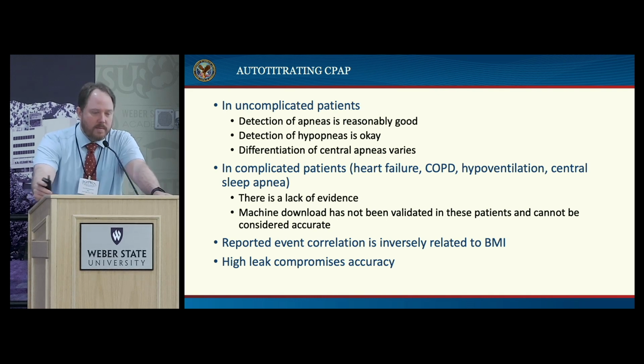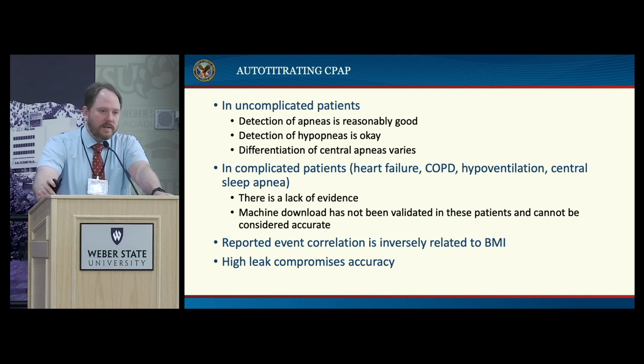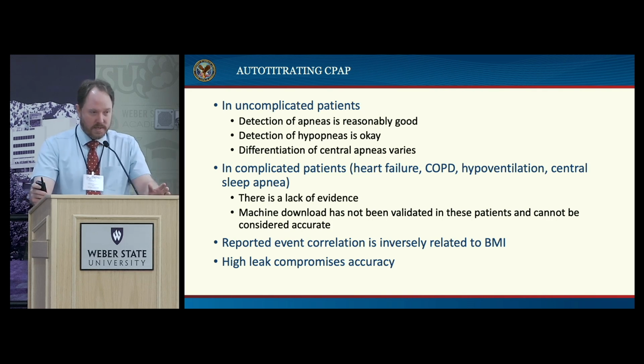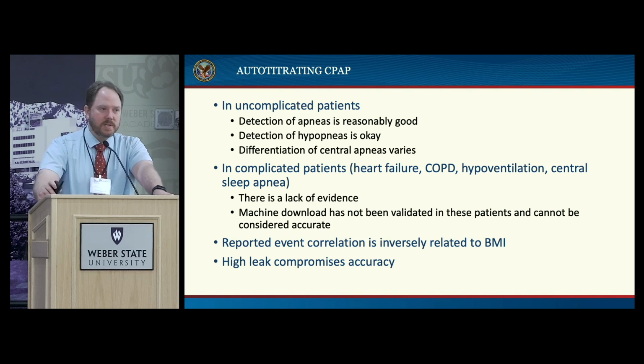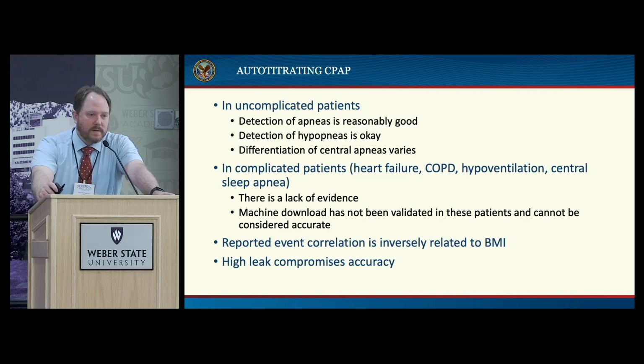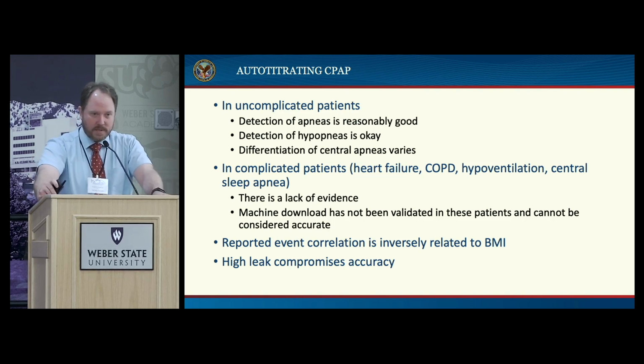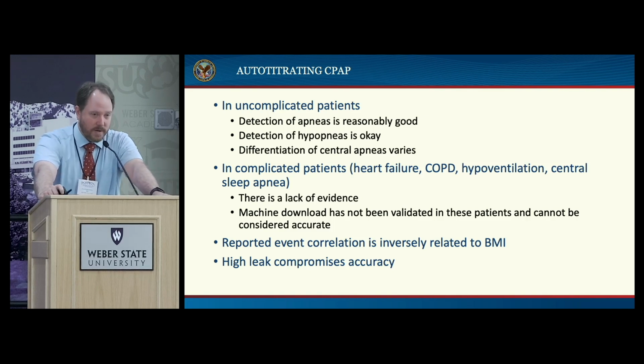The other important fact about this is if there's a lot of leak, then the numbers are meaningless. The signal-to-noise ratio is unfavorable, and the machine's data is compromised. And so if the leak is high, and for most machines, the magic number is 25 or 24, if the leak number you see is above that, then you can just ignore everything else the machine says. It's not worth your time looking at it because you're not going to be able to make sense of it.